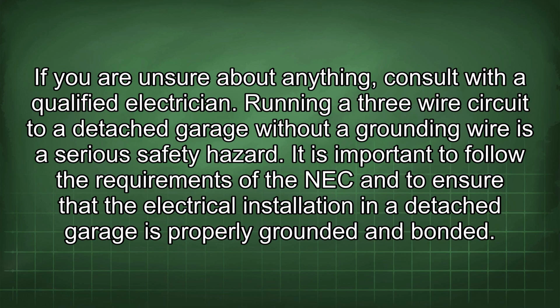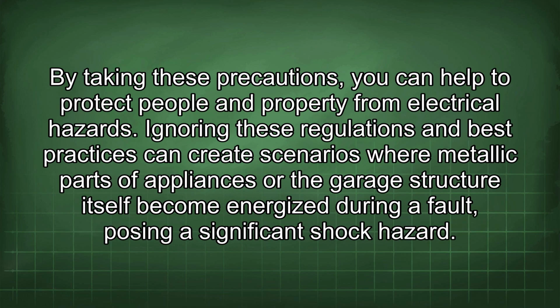Running a 3-wire circuit to a detached garage without a grounding wire is a serious safety hazard. It is important to follow the requirements of the NEC and to ensure that the electrical installation in a detached garage is properly grounded and bonded. By taking these precautions, you can help to protect people and property from electrical hazards. Ignoring these regulations and best practices can create scenarios where metallic parts of appliances or the garage structure itself become energized during a fault, posing a significant shock hazard.